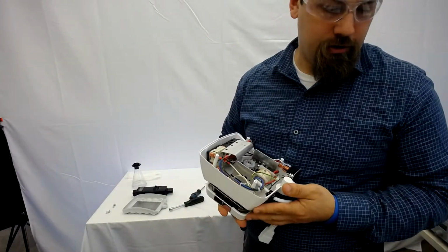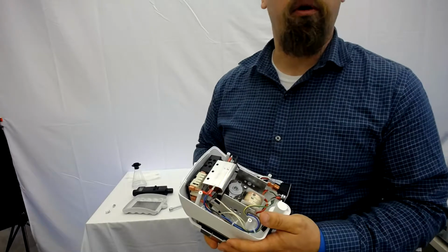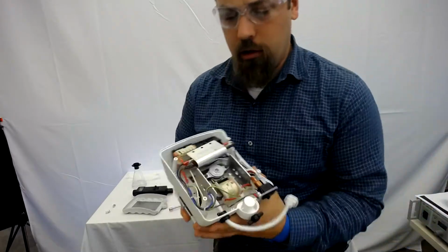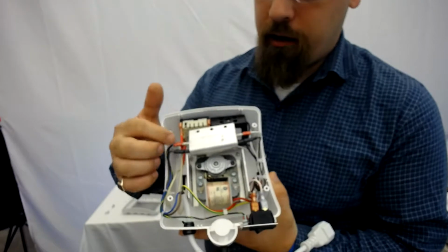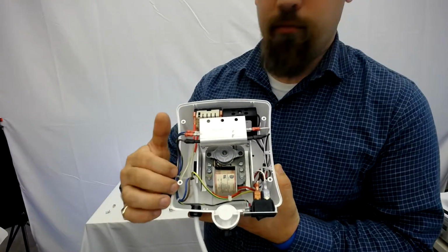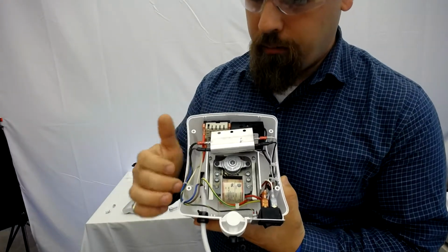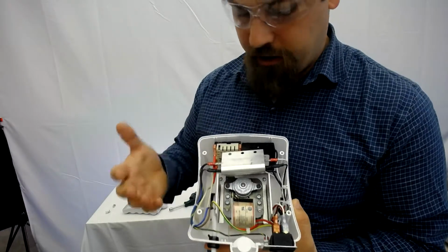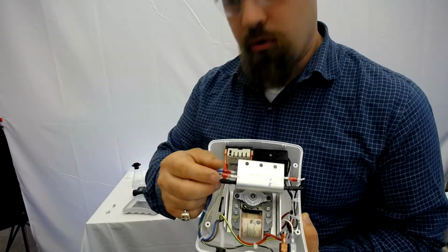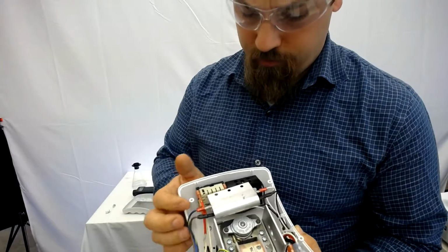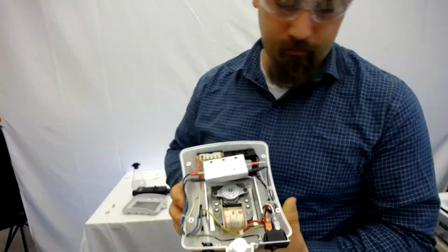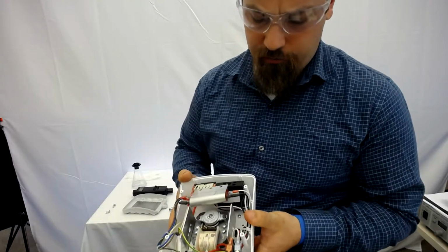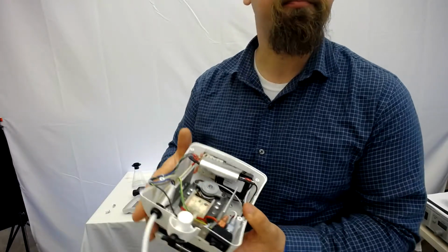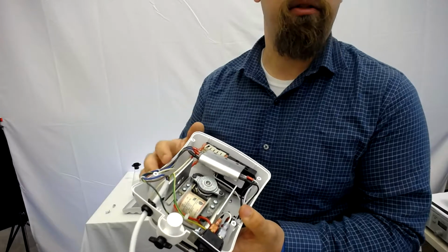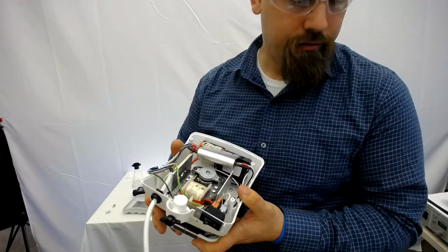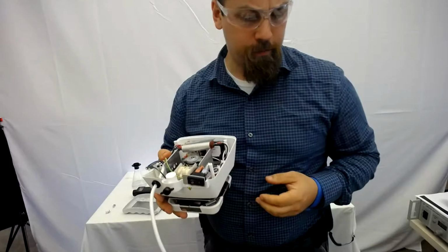So now for calibration, before we get to calibration, we're going to do a workmanship check. So we're going to look inside and make sure all the wires are routed correctly. Make sure they're wire tied, make sure nothing's rubbing, make sure all the connections are tight. And particularly what we're looking for is that no wires are going to be around the motor. So there's no danger of the wires being caught up in the motor.